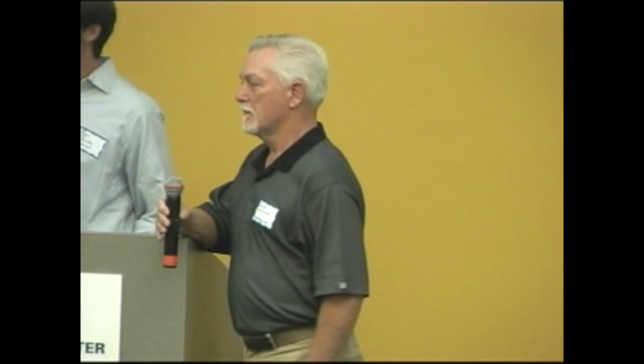Yeah, part of the answer to your question is some of the work that's already been done with PG&E and UC Davis from the cooling center standpoint. There is this calculation tool that does take all the California climate zones into the equation. Both SMUD and PG&E have tested the product, and they both have used water meters to determine water consumption. Our test is about to be concluded. It's the second year of testing. The basic question that we had was in the fall or spring when there were low loads, it seemed to use more energy, more fan energy. And so that's why we went through a second year of analysis. I don't have that data yet. I have a third party that's going to be analyzing it and reporting that to me, but that's forthcoming shortly.